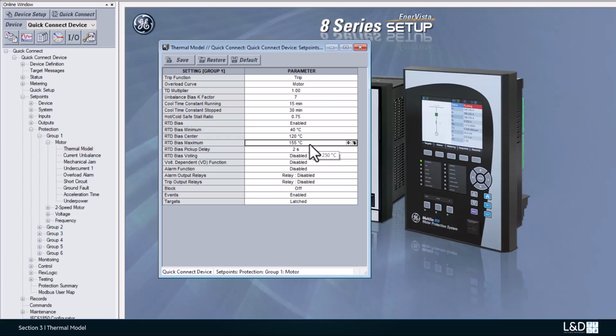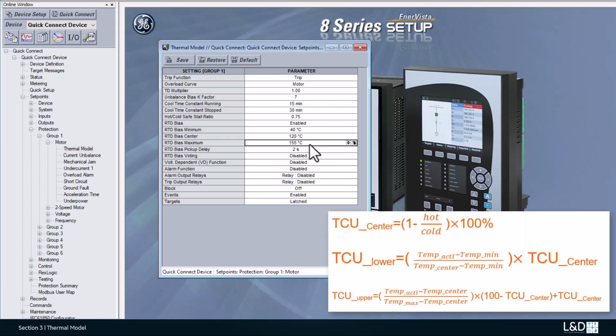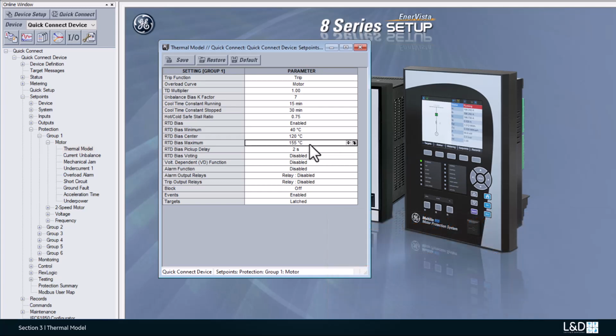Once min, max, and mid temperature are set, the corresponding TCU can be calculated with this equation, and the motor thermal capacity used will be displayed as the higher value of the RTD and unbalanced current bias calculated by the TCU. But only the RTD bias will not make the relay trip. It must have that current level higher than the overload pickup.